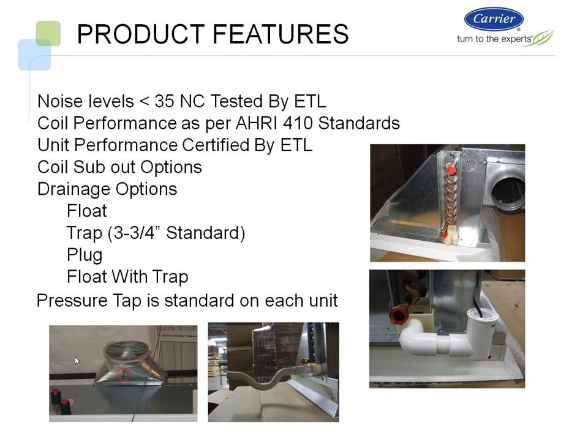And I'll give you an example of why that's important. Typically a balancer, when they go in on a VAV system or actually on a chill beam system, they'll poke a hole in the duct, they'll take the reading, and hopefully they'll plug that hole.